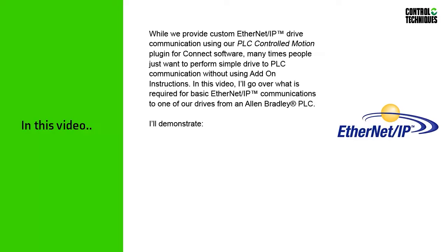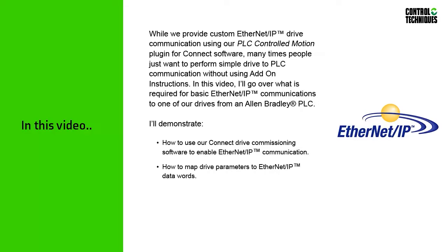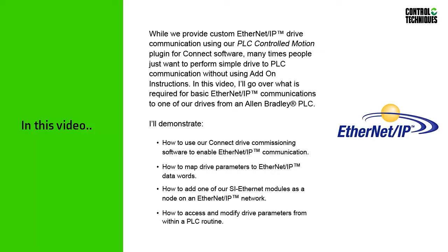an Allen Bradley PLC. I'll demonstrate how to use our Connect drive commissioning software to enable EtherNet IP communication, how to map drive parameters to EtherNet IP data words, how to add one of our SI Ethernet modules as a node on an Ethernet IP network, and how to access and modify drive parameters from within a PLC routine. So if you're ready, let's get started.